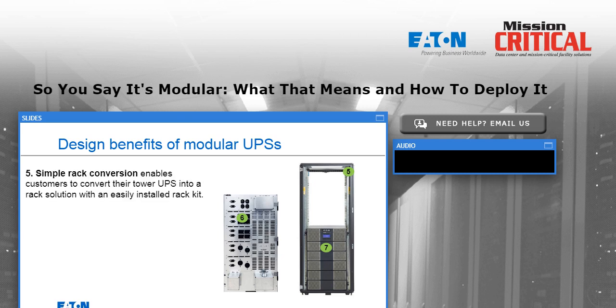So it is also possible to take a standalone modular UPS like this small one shown here and deploy it in an IT equipment rack. So a conversion kit would allow that UPS to be mounted in your own rack as shown in the picture on the far right. And again, I can populate and depopulate power modules and battery modules as necessary. And as you can see, I can choose things like the power cable that I need on the input of this UPS and any receptacles that I want to populate on the output.